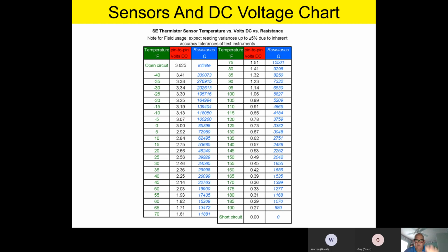And so you can look at this chart and see that as the temperature changes, the voltage pin to pin changes, and the ohms change based on the temperature. Now, if I take that sensor off the board, the open circuit voltage in the upper left-hand corner of this chart tells you open circuit. What that means is, if I pull the sensor off the board and read the voltage on the pins that the sensor plugged onto, it should read 3.625 volts DC without the sensor plugged on. And then according to temperature, you'll read a different voltage, and a different resistance on each sensor.